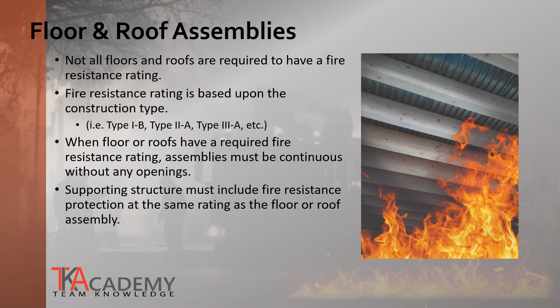The goal is to prevent propagation of flames and smoke from one level to another. However, vertical openings between 2 stories that are not concealed with the construction are allowed. When the vertical opening is more than 2 stories, it is considered an atrium and is subject to other code requirements. Shafts are enclosed vertical connections between openings through horizontal assemblies such as floors or roofs. Shafts are common in buildings, especially with stairwells and elevators, but also with chases for mechanical ducts and piping.